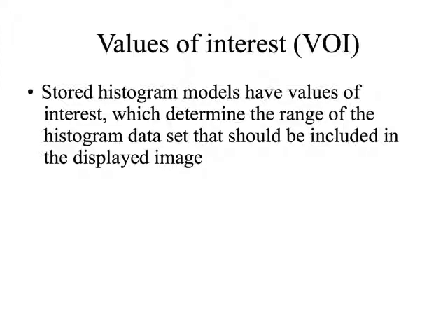One of the ways it does that is it's going to suggest certain values of interest, right? And we can actually change these values of interest after the fact. But the stored histogram models have values of interest, right? They're going to have, for instance, with that chest x-ray, a peak and a trough. And so those values of interest are going to relate to how the displayed image is eventually generated, right?